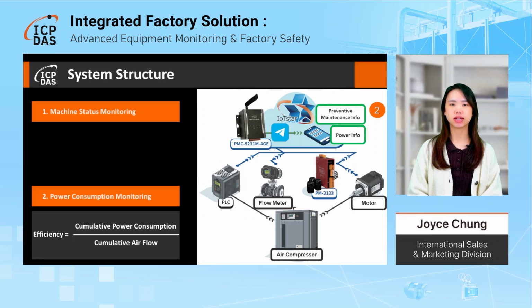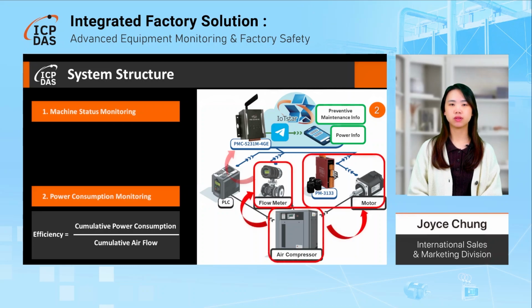Let's move on to the second section, power consumption monitoring. The PMC5231M4GE gathers cumulative airflow data from flow meters and power usage information from the PM3133 power meters. By calculating the efficiency value, the customer can understand how much energy is consumed to produce 1 cubic meter of compressor air. This efficiency value is calculated and sent to the customer via the Telegram app for review at the start of each month.